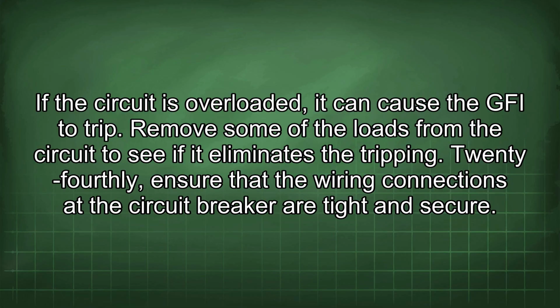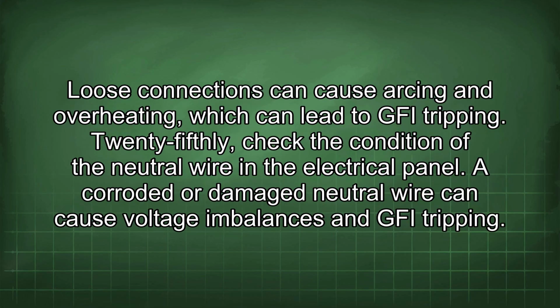24thly, ensure that the wiring connections at the circuit breaker are tight and secure. Loose connections can cause arcing and overheating, which can lead to GFI tripping. 25thly, check the condition of the neutral wire in the electrical panel. A corroded or damaged neutral wire can cause voltage imbalances and GFI tripping.